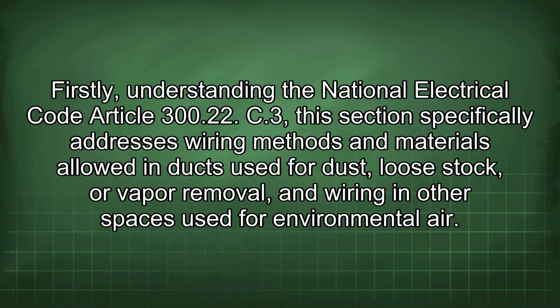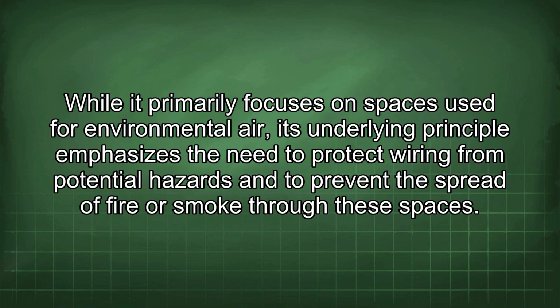Firstly, understanding the National Electrical Code Article 300.22 C3. This section specifically addresses wiring methods and materials allowed in ducts used for dust, loose stock, or vapor removal, and wiring in other spaces used for environmental air. While it primarily focuses on spaces used for environmental air, its underlying principle emphasizes the need to protect wiring from potential hazards and to prevent the spread of fire or smoke through these spaces.